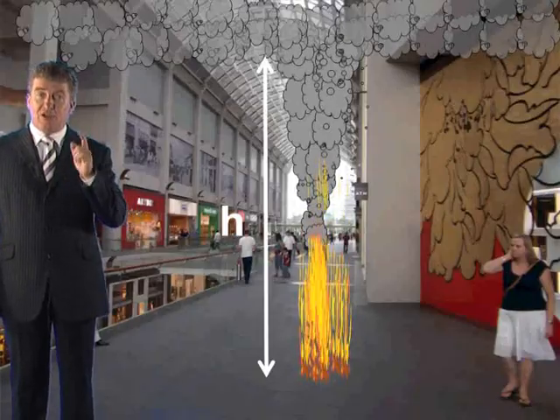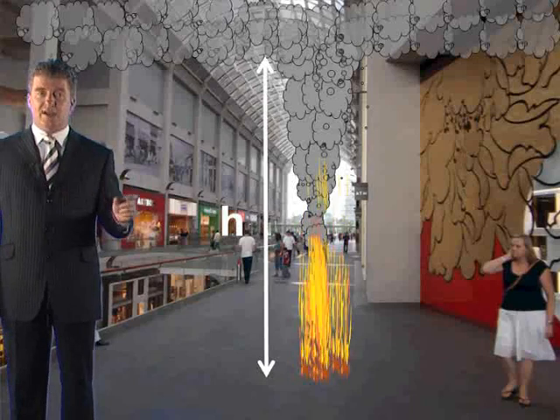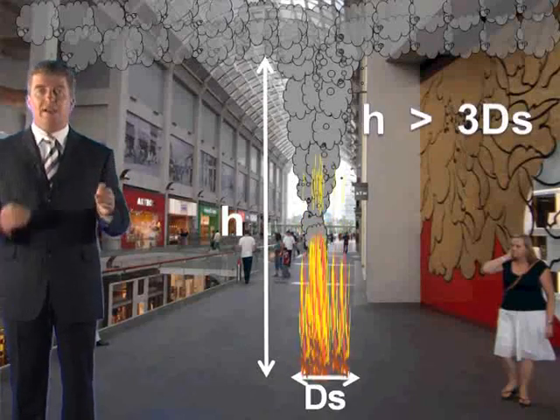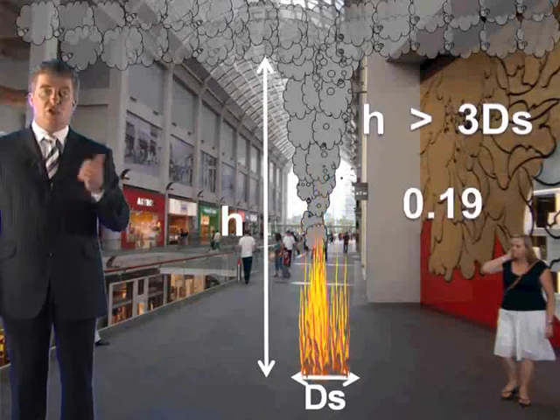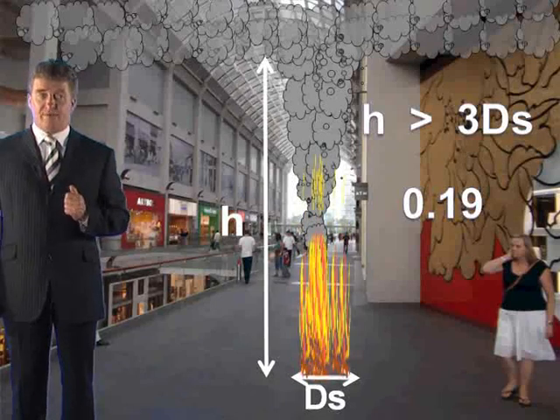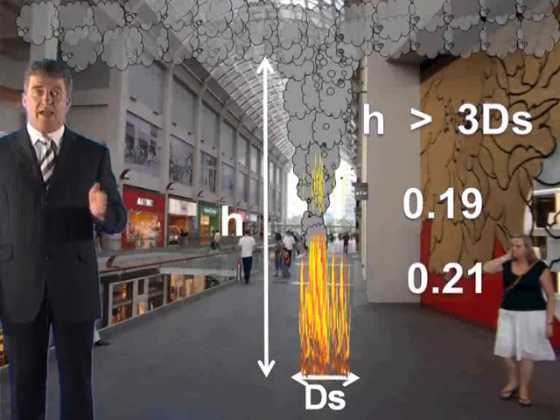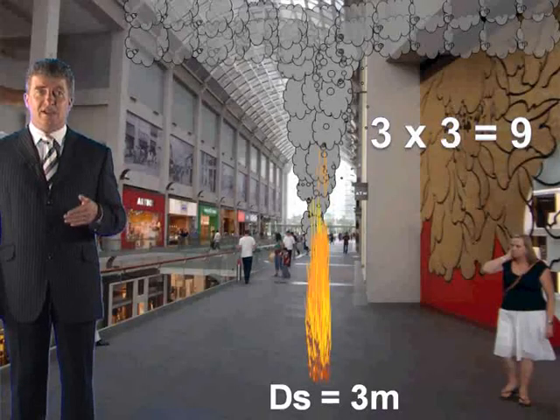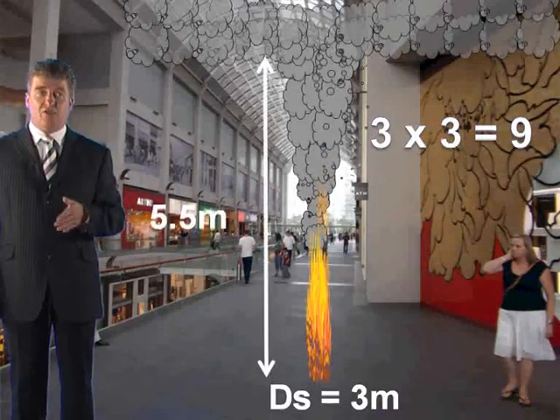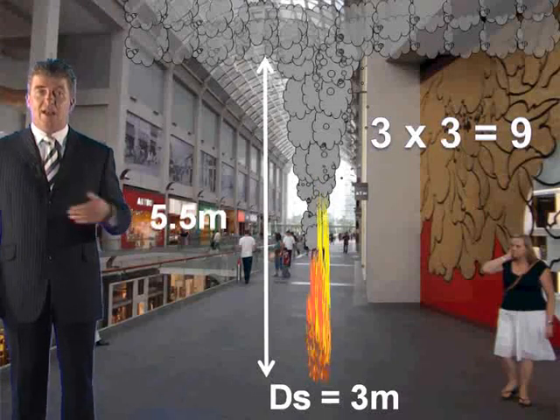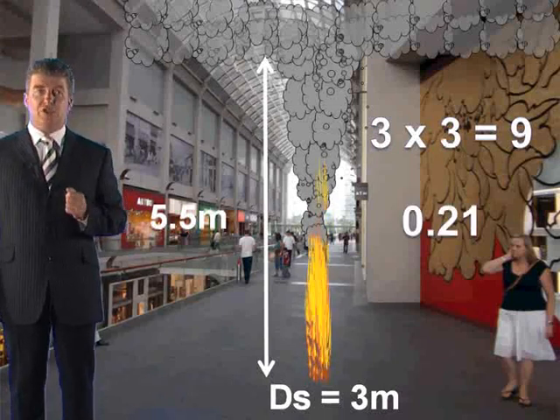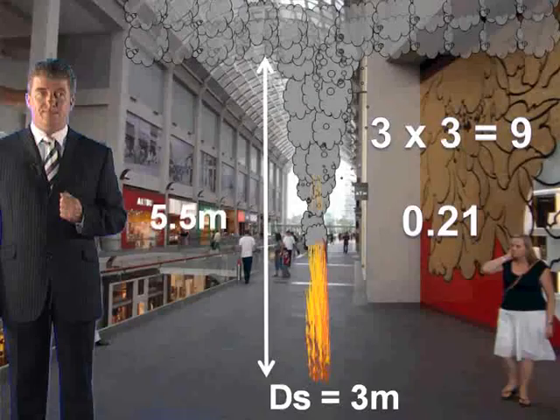Again, if the clear layer height is greater than 3 times the longest dimension of that source, you use 0.19 as the coefficient. If not, you apply 0.21. Now, in this case, 3 times 3 is 9 metres. Clearly, this is greater than the clear layer height. Therefore, you apply 0.21 as the coefficient. So this is 0.21 to apply.